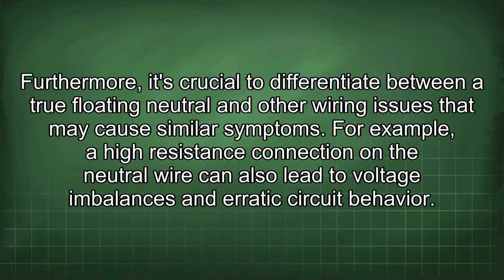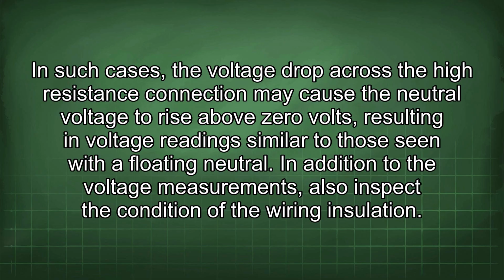Furthermore, it's crucial to differentiate between a true floating neutral and other wiring issues that may cause similar symptoms. For example, a high resistance connection on the neutral wire can also lead to voltage imbalances and erratic circuit behavior. In such cases, the voltage drop across the high resistance connection may cause the neutral voltage to rise above 0 volts, resulting in voltage readings similar to those seen with a floating neutral.